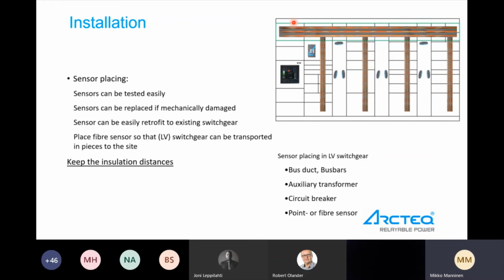Also, sensors in the bus duct. Quite typically, there is a bus duct or cabling to the transformer, and in that case, normally the overcurrent is measured from the transformer end, and then the sensors or the fiber can be mounted to the bus duct. Another option is to measure the current from the board itself, and then have the pressure sensor in this cable end or the bus duct end. And typically also a point sensor for the circuit breaker, and sometimes also for the auxiliary transformer, which may be, for example, inside here.